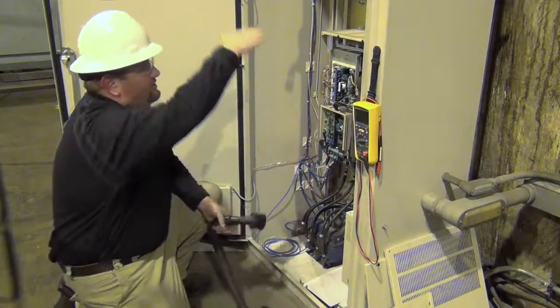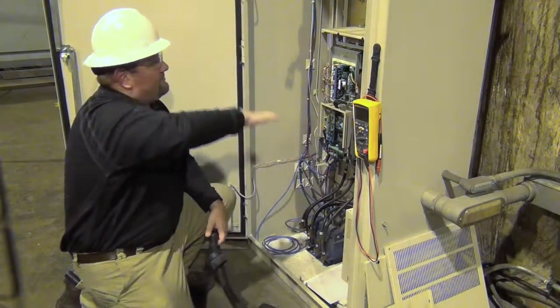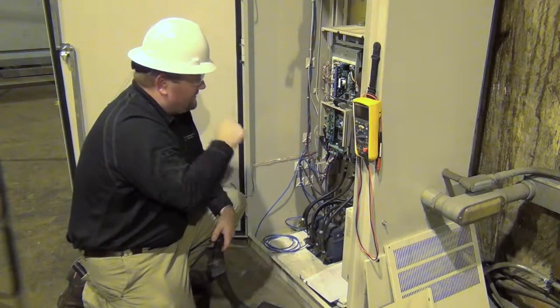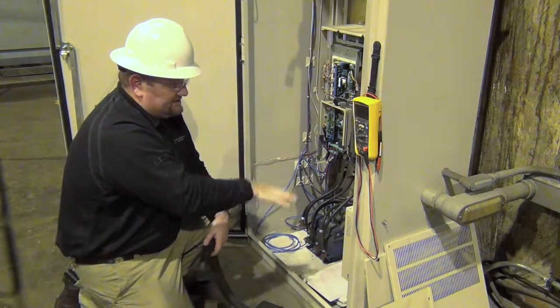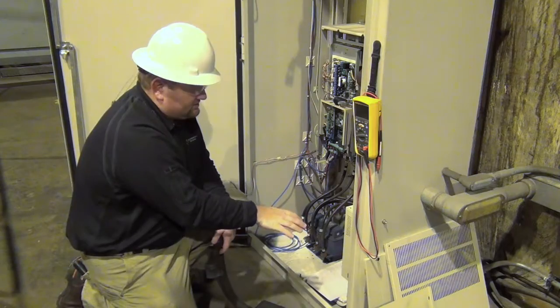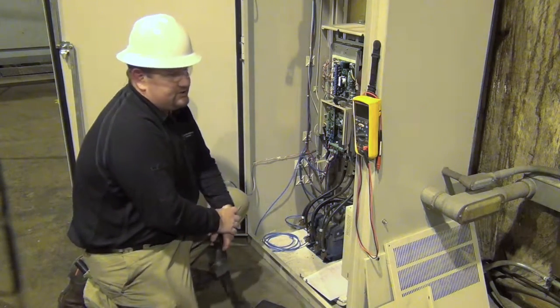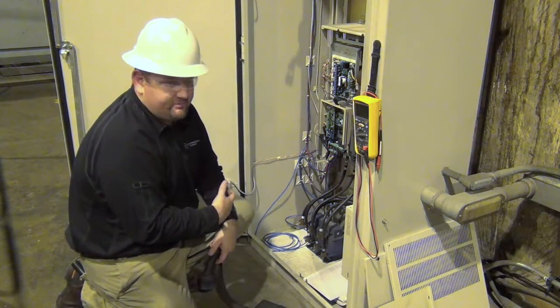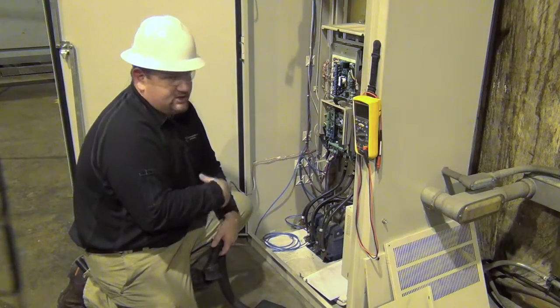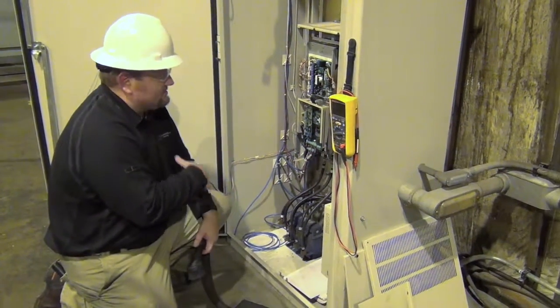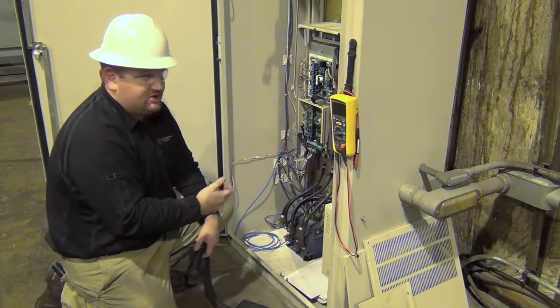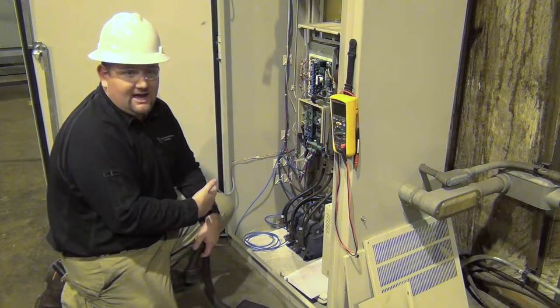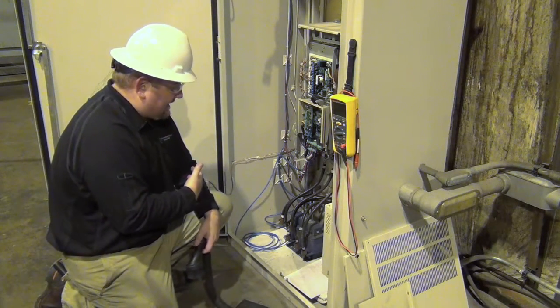Okay, so now that we've blown a lot of the loose dust from the top of the drive down towards the bottom, we've given it a little bit of time, let some of that dust settle in the lower sections. The primary thing we're trying to do with the air is loosen up the debris and get debris that's on crevices of wires or in very difficult places to reach down and out, so we have the highest likelihood of getting them picked out of the drive.